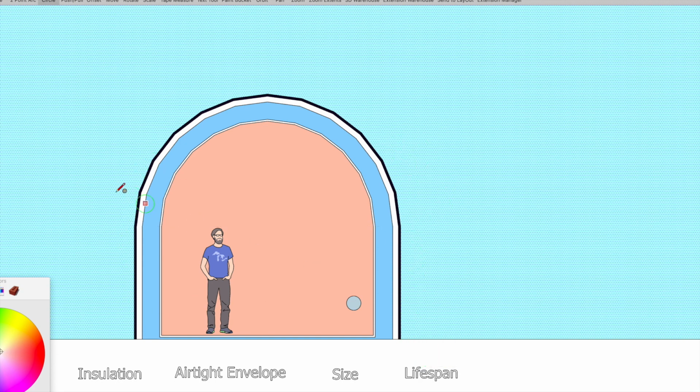So what happens is, as the wind blows, it comes in all the tiny holes on this side of your building with fresh air, and pushes out all the tiny holes on this side of the building and brings fresh air into the building effectively. But it takes all of the heat of the building. So there's little or no point in having really good insulation if you don't have an airtight envelope.